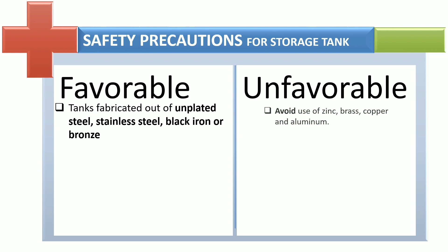Tanks fabricated out of mild steel, stainless steel, black iron or bronze can be used for storage of ethanol, since they have acceptable resistance to corrosion by ethanol. Avoid use of zinc, brass, copper and aluminum for ethanol. Non-metallic materials such as butadiene, neoprene rubber, polyethylene, nitrile, polypropylene, Viton and Teflon are resistant to ethanol. Tanks shall be constructed of low carbon or cold finished steel with butt welding. It is advised to not use any plated material for tank construction.